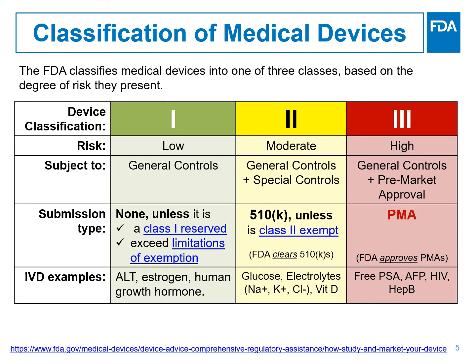Most Class 3 devices require a pre-market approval, or PMA. The PMA is the most stringent type of pre-market submission. Before the FDA approves a PMA, the sponsor must provide valid scientific evidence demonstrating reasonable assurance of safety and effectiveness for the device's intended use. Some IVDs that fall under this classification are assays intended to detect, for example, free PSA, alpha-fetoprotein, HIV, and hepatitis B.